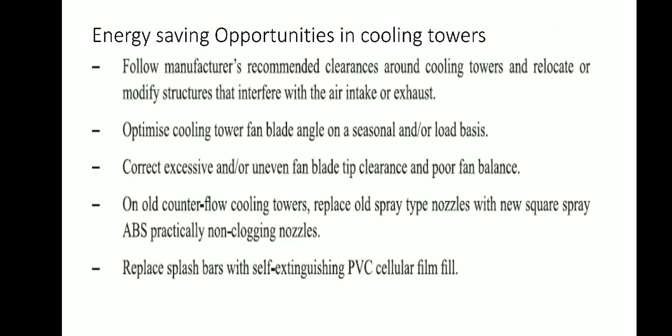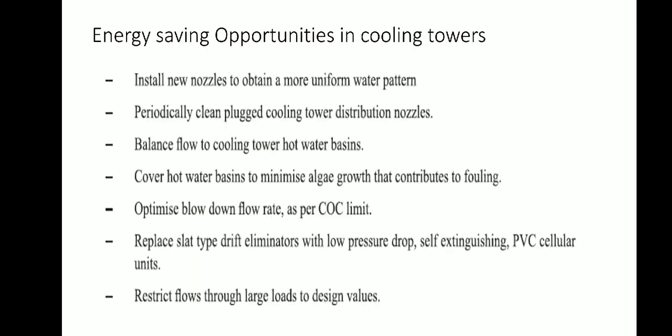On old counterflow cooling towers, replace old spray type nozzles with new square spray ABS practically non-clogging nozzles. Replace splash bars with self-extinguishing PVC cellular film. Install new nozzles to obtain more uniform water pattern.